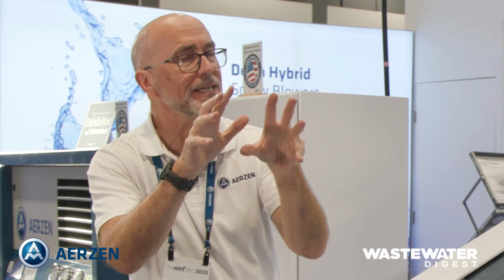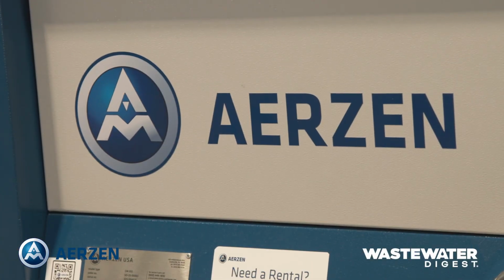Because of the way that operates, the pressure in the header that those blowers see can be 1 to 2 psi higher than what the system actually needs, meaning what the system would need based on the depth of the water and whatever losses there are in the pipes and in the diffusers. And so you're basically wasting another 10 to 15%. So how do you knock that down?